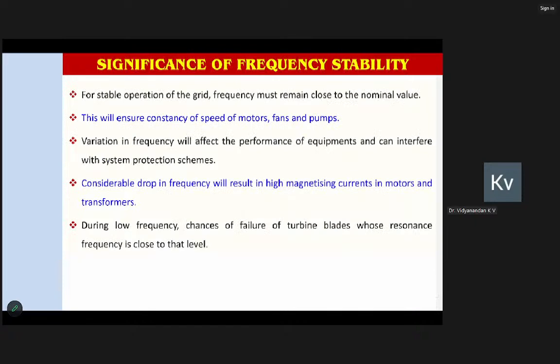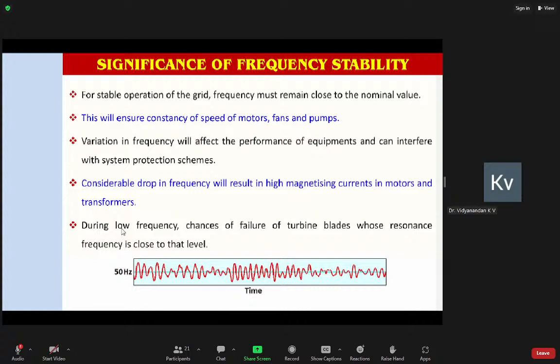First of all, I have already mentioned frequency is a dynamic parameter. It will never remain constant. So since it is a dynamic parameter, we have to accept that it has to fluctuate. But the thing is, we cannot afford or allow the frequency to deviate too much.